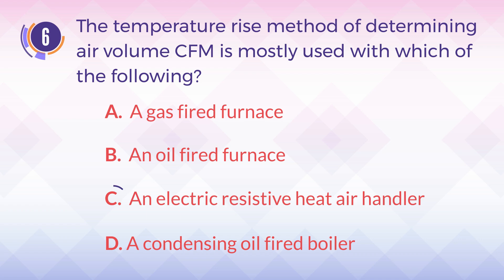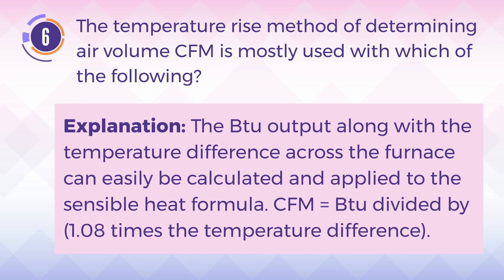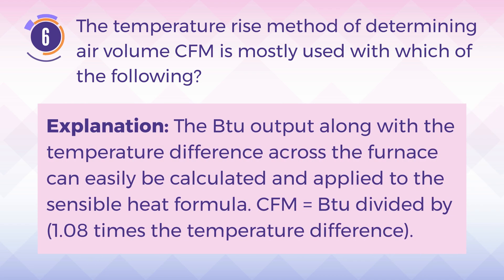The answer is C. Electric-resistive heat air handler. Explanation: The BTU output along with the temperature difference across the furnace can easily be calculated and applied to the sensible heat formula. CFM equals BTU divided by 1.08 times the temperature difference.